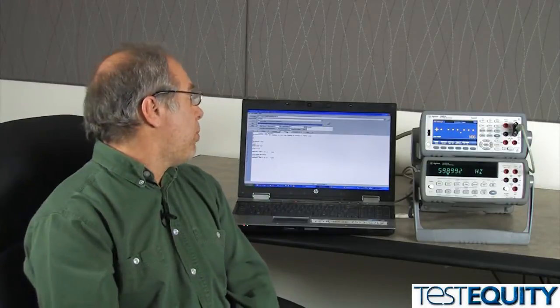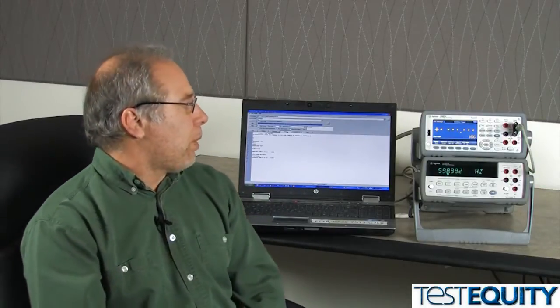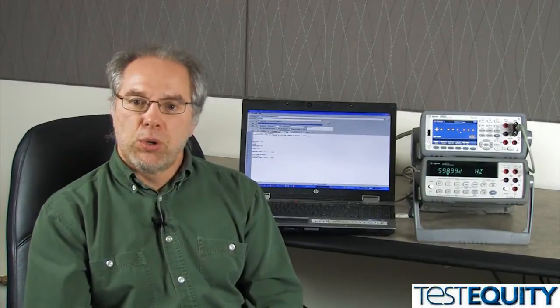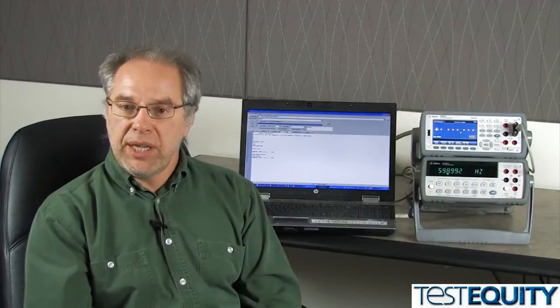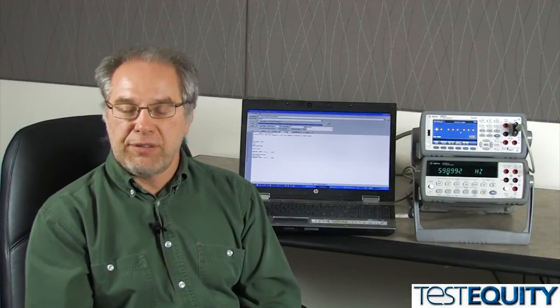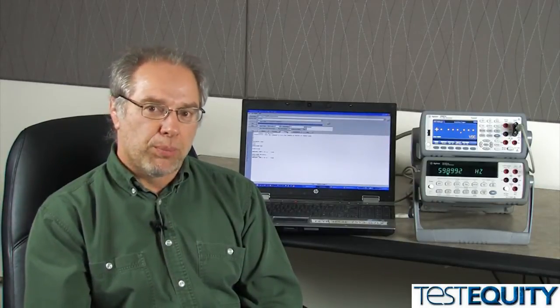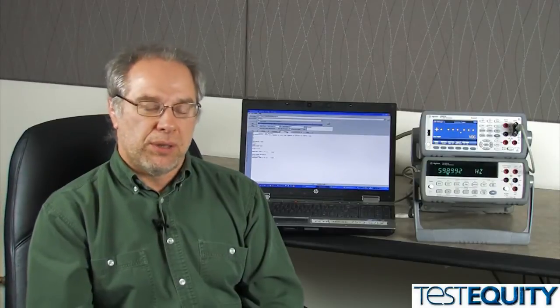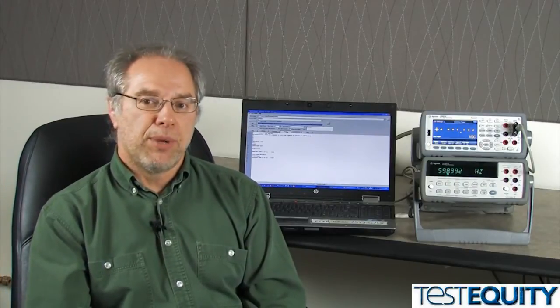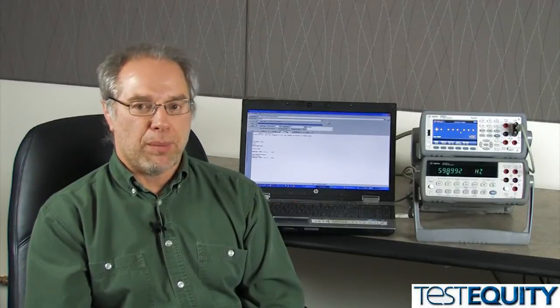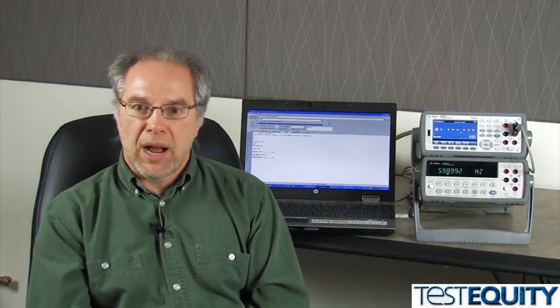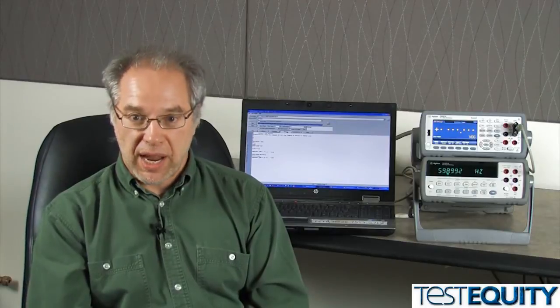So what I'm going to do here is run a little program that will query the new 34461A. It'll come back and tell me its identification, and then I will program the DMM to emulate the 34401A, and the IDN from after programming it will now be the 34401A.